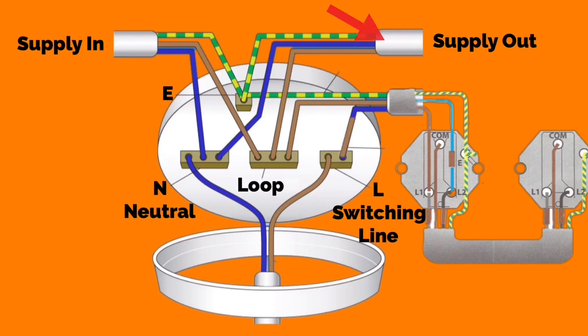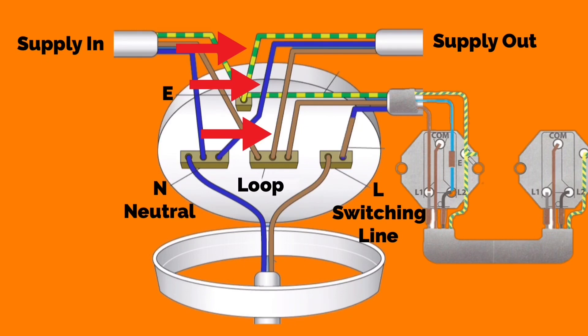The cable in the top right now goes into another room and repeats the process again. It takes a permanent line, neutral, and circuit protective conductor into the next ceiling rose, terminated in the loop terminal for the line, the neutral terminal, and the earth terminal within the accessory, and the process is repeated again.